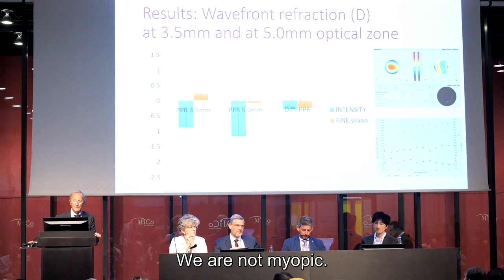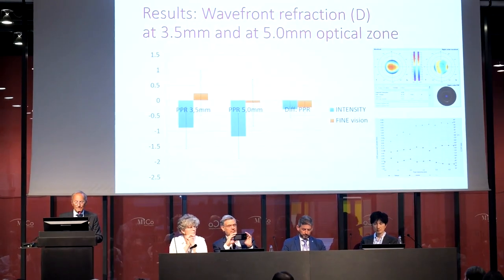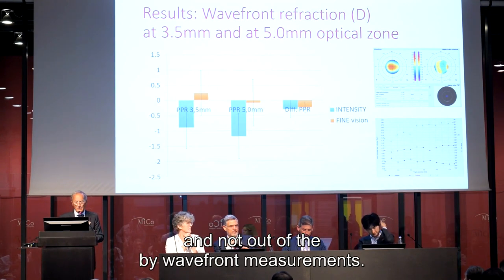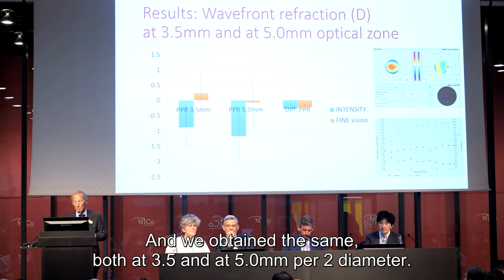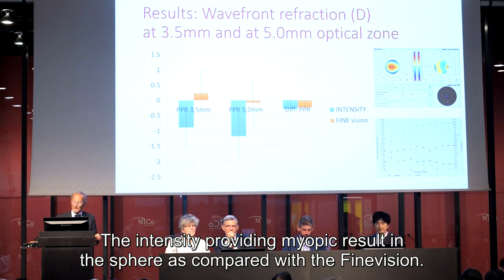About the wavefront refraction, as you know, we can obtain refraction from a pupil area rather than just a circumference by wavefront measurement. We obtained the same result — both at 3.5 and at 5 mm aperture diameter — with the Intensity providing a myopic result in sphere as compared with the Fine Vision.